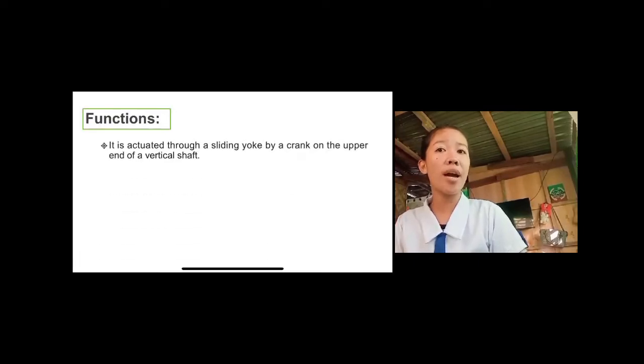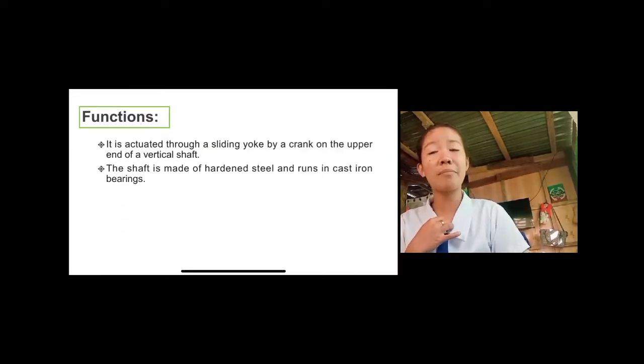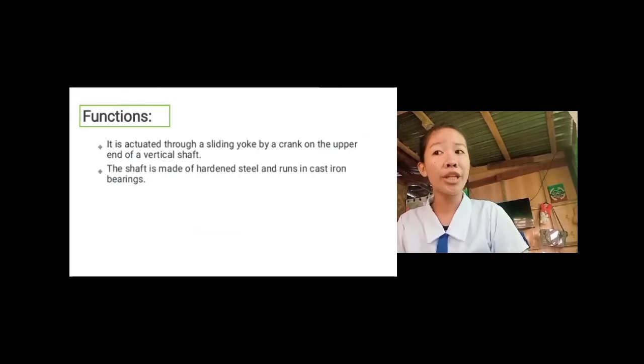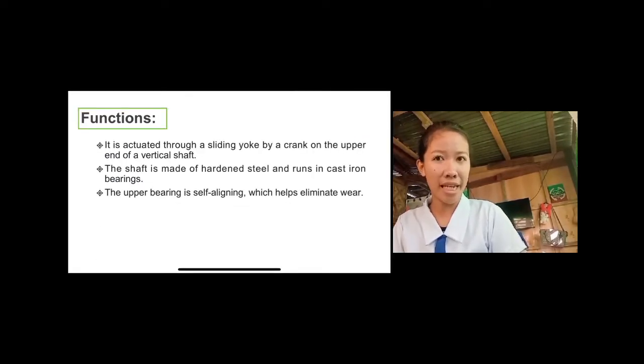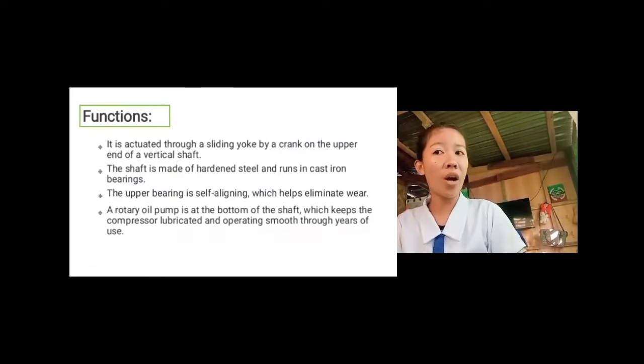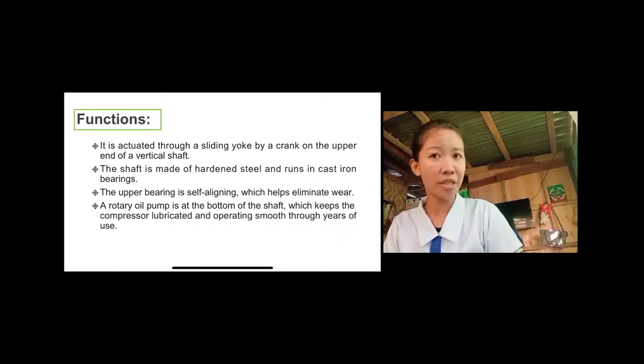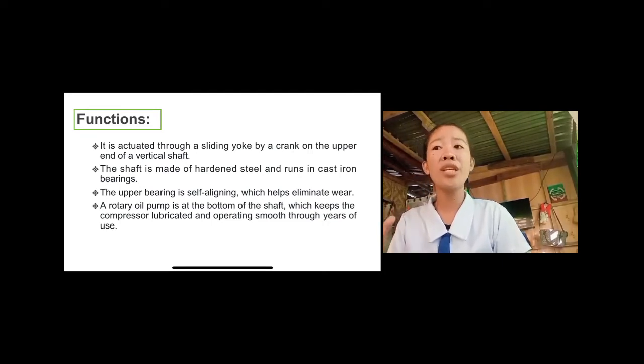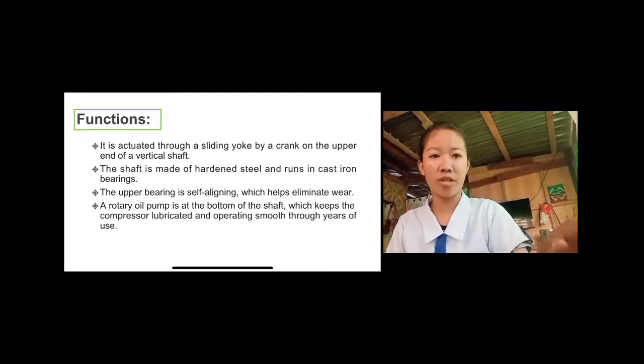One, it is actuated through a sliding yoke by a crank on the upper end of a vertical shaft. Second, the shaft is made of hardened steel and runs in cast iron bearings. Third, the upper bearing is self-aligning, which helps eliminate wear. And lastly, a rotary oil pump is at the bottom of the shaft, which keeps the compressor lubricated and operating smoothly through years of use. So these four functions are found in the reciprocating compressors.